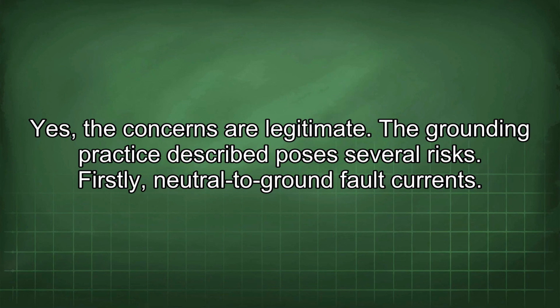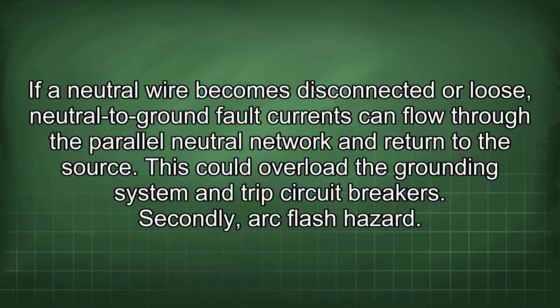Yes, the concerns are legitimate. The grounding practice described poses several risks. Firstly, neutral to ground fault currents. If a neutral wire becomes disconnected or loose, neutral to ground fault currents can flow through the parallel neutral network and return to the source. This could overload the grounding system and trip circuit breakers.